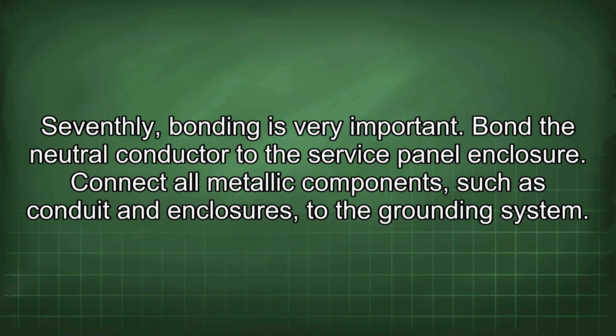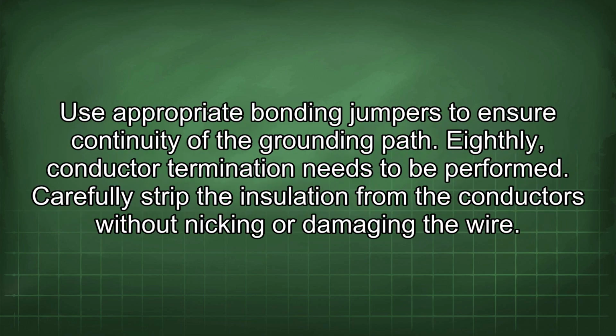Seventhly, bonding is very important. Bond the neutral conductor to the service panel enclosure. Connect all metallic components, such as conduit and enclosures, to the grounding system. Use appropriate bonding jumpers to ensure continuity of the grounding path.